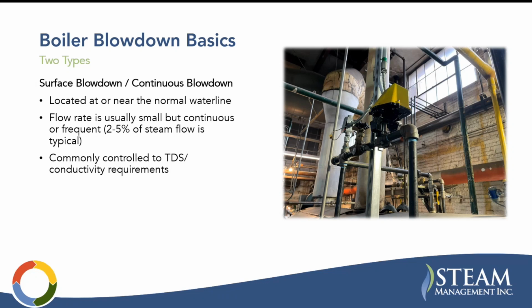So this is a strategically located blowdown, continuous or at least frequent. And 2 to 5% of steam flow is typical for a well-maintained system with good condensate return. It's commonly controlled by TDS, which is typically measured with conductivity. So you're talking about a lot of metals left in the water, and the more metals there are, the more conductive the water is. So it's actually measured with conductivity.